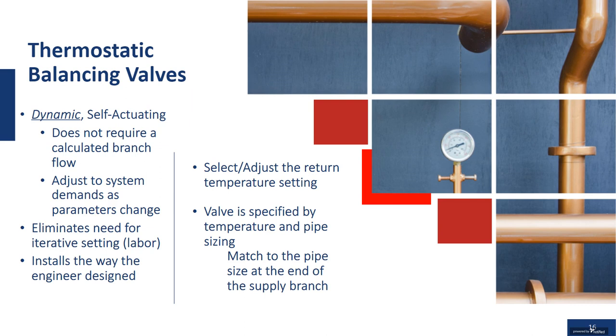Basically, what you have to do is, if it's a fixed temperature thermostatic valve, you basically have to select what return temperature you're looking for. If it's an adjustable thermostatic balancing valve, you have to adjust that valve to whatever return temperature you're looking for.